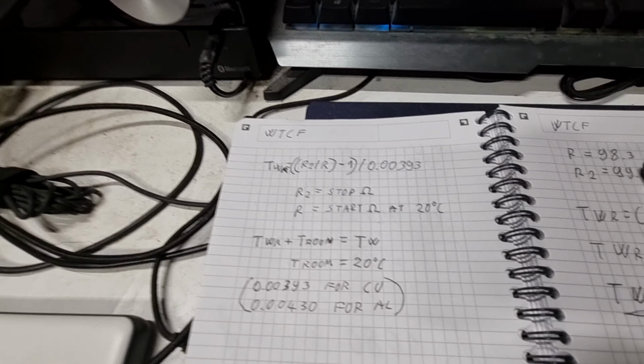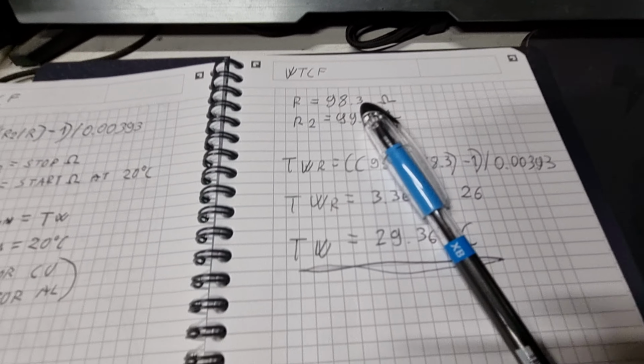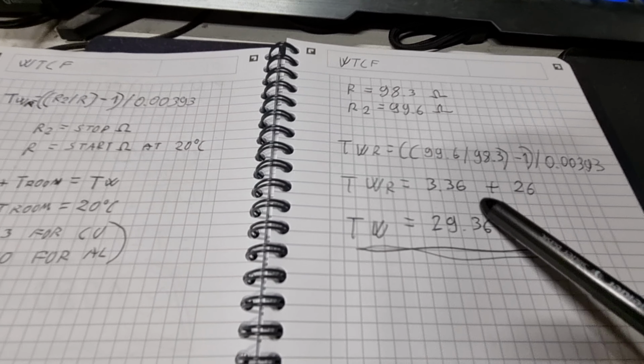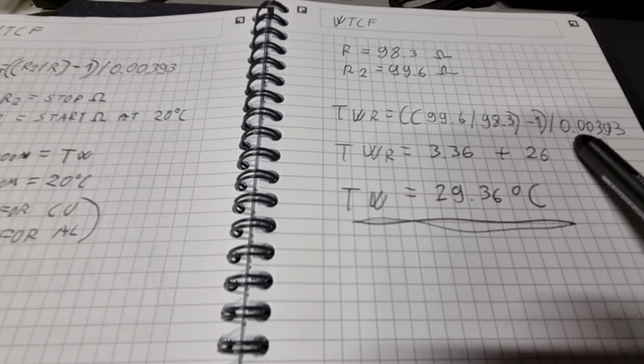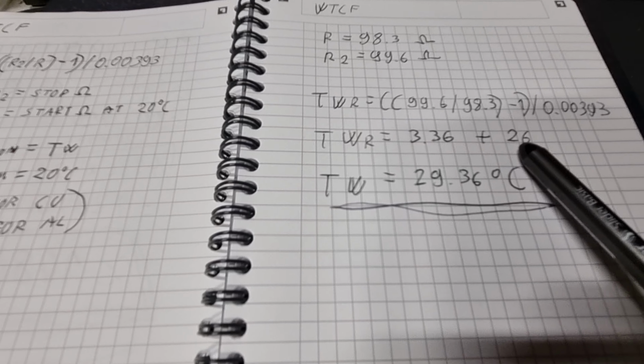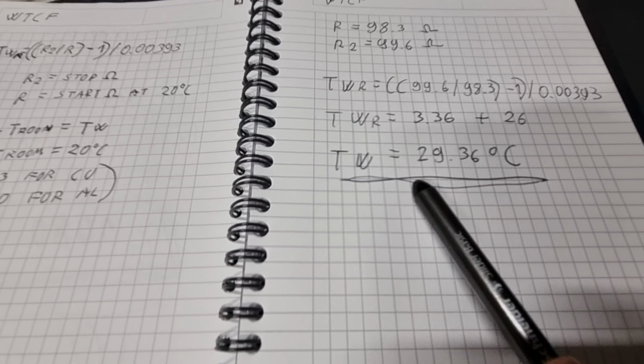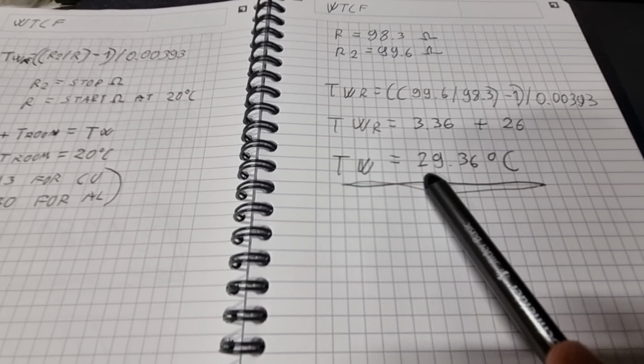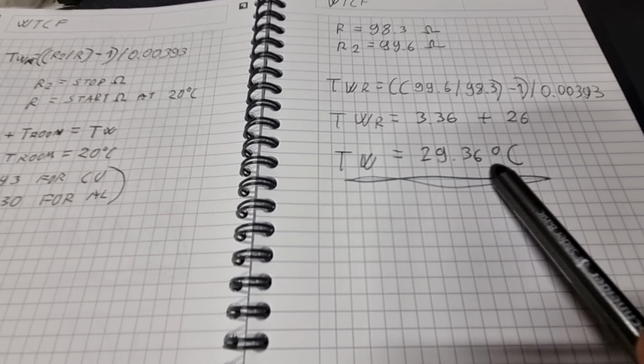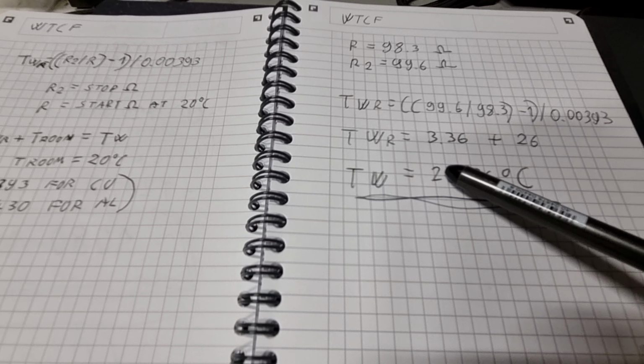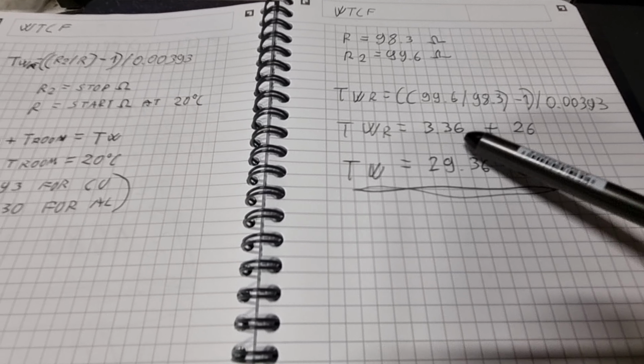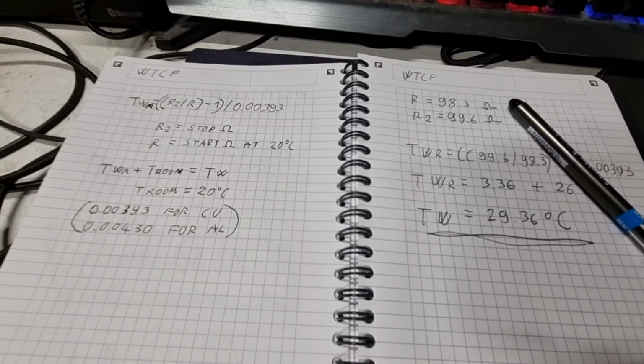So now, after we calculated this using the formula, with room temperature at 26 C, we found that the temperature inside of the transformer is 29.36 C, so about 3.36 degrees above ambient.